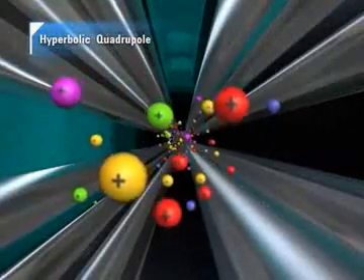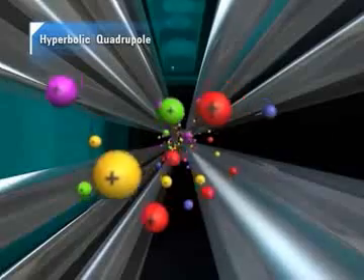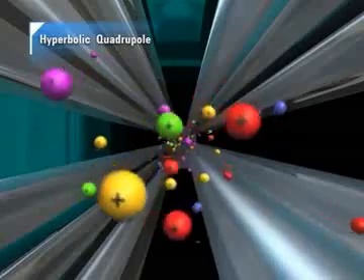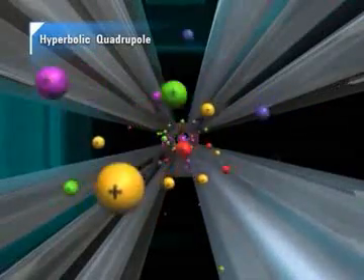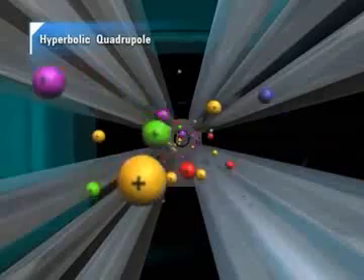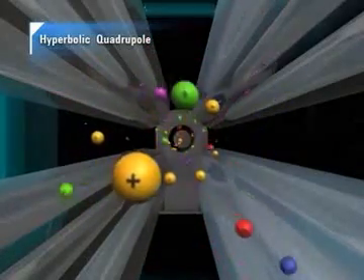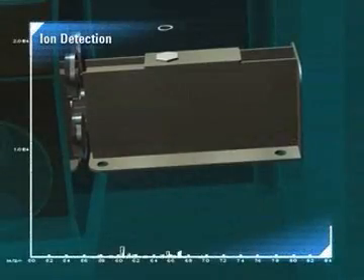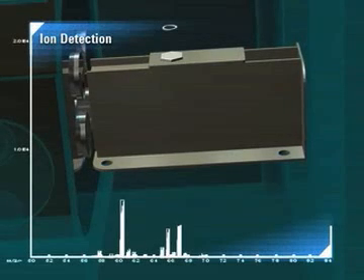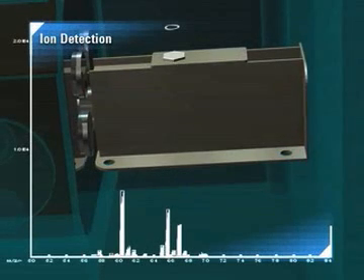The analyte ions leaving the ORS cell enter the quadrupole mass filter and are separated based on their mass-to-charge ratio. Only the target ion is stable and passes along the axis of the quadrupole. The quadrupole scans rapidly across the mass range and passes each mass of interest sequentially to the electron multiplier detector. Ions strike the detector and the resulting electronic signals are processed by the detector electronics and stored in a multi-channel scalar, creating a mass spectrum where intensity at a given mass is proportional to concentration of the isotope at that mass.